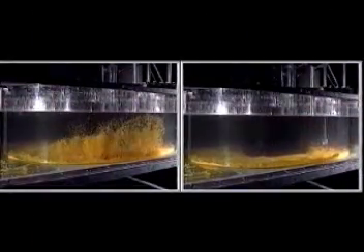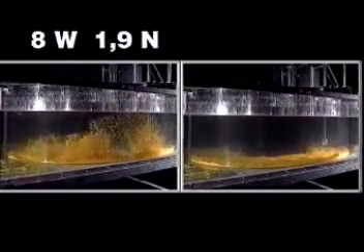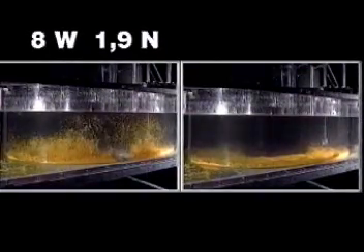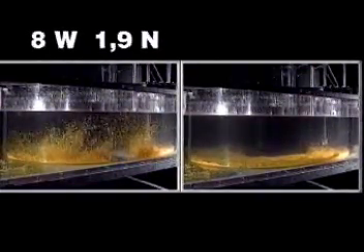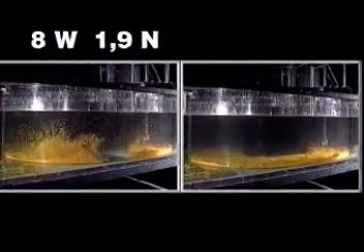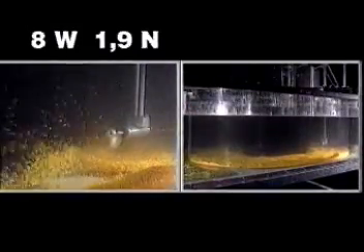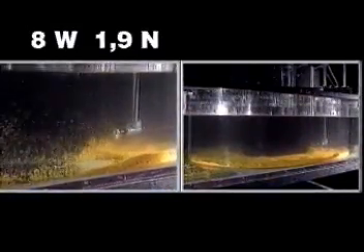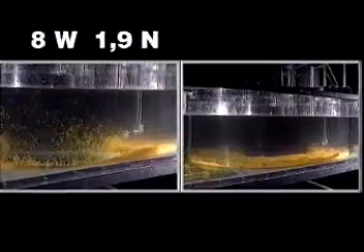A side view of the mixers in action makes it easier to see how the two machines with equal power inputs can have such dramatically different effects. Movement around the poor propeller shows a lot of energy going into the surrounding water. There's even some good scouring occurring immediately in front of the propeller, but a dune of settled particles is building up not far downstream.